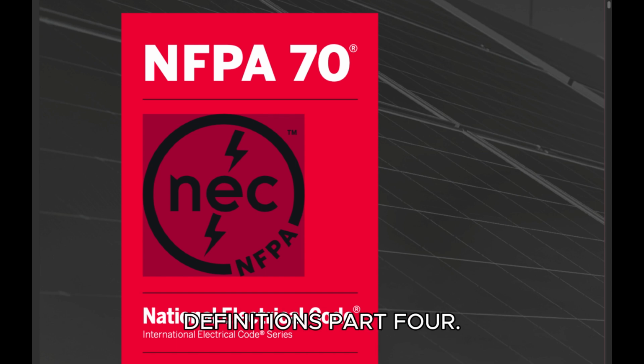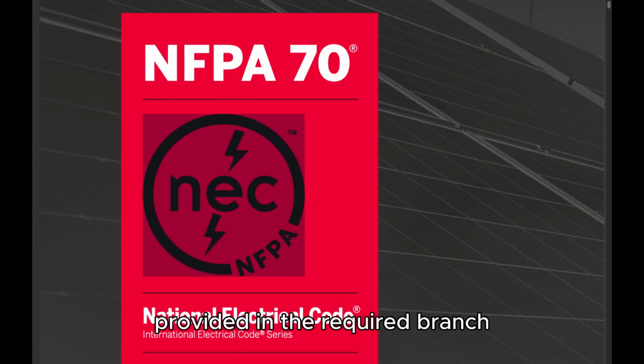Article 100 Definitions Part 4. Overcurrent protective device, supplementary. A device intended to provide limited overcurrent protection for specific applications and utilization equipment such as luminaires and appliances. This limited protection is in addition to the protection provided in the required branch circuit by the branch circuit overcurrent protective device.